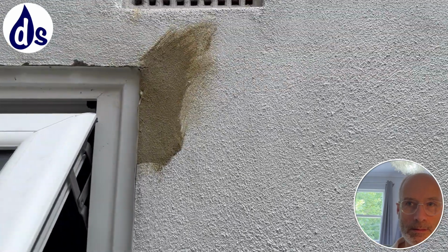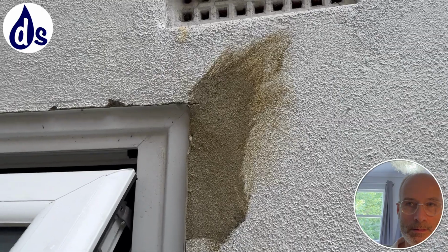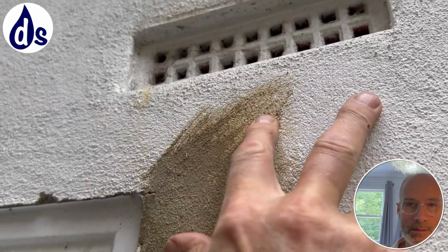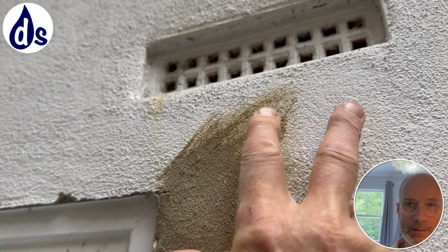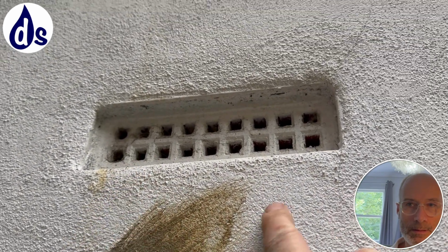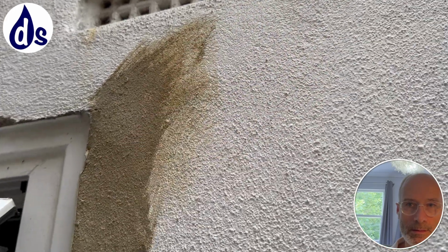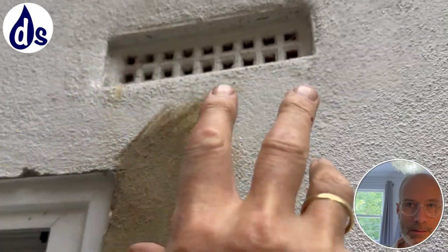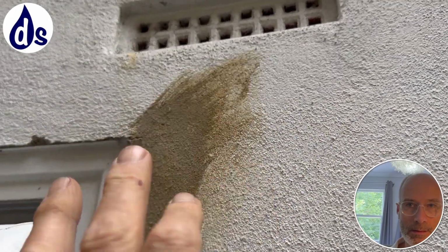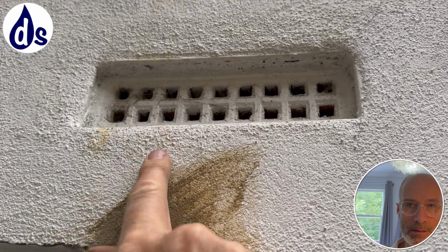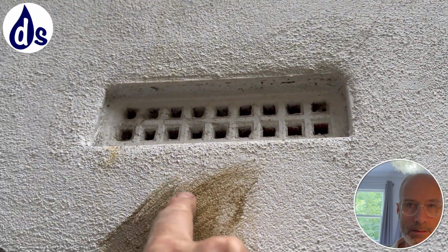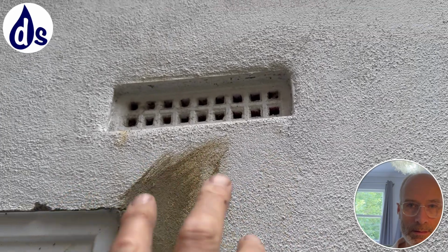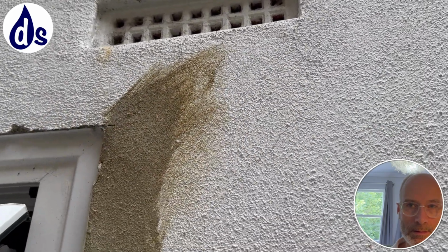Looking on the outside, we can see that what would have been a bigger air brick probably has been replaced with a small air brick, and it needs to be opened up. Ideally you get one with a flap, which will be a circular hole there and a flap, and you have to get somebody to neaten this up a bit. But this needs to be cut out, a circle about 10 centimetres, and then you've got a through hole.